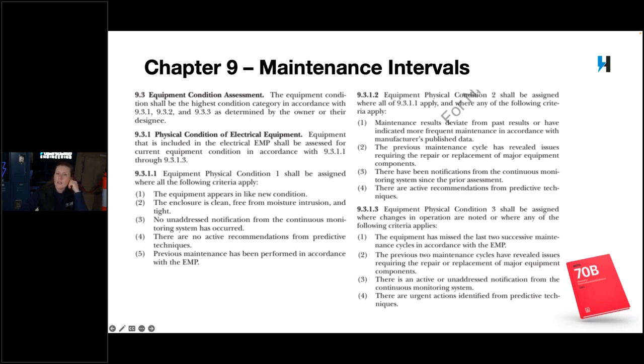Condition 2 is that there might have been something wrong - it's had a maintenance result that deviated from past results, indicating a potential problem that's beginning or has already happened, and we need to check on this a little more often. A lot of the other maintenance requirements decrease the time frame - you're doing it more often for condition 2 - but for infrared, it's still just your annual thing. That's bare minimum, by the way. Condition 3, though, if you've missed the last 2 required maintenance cycles according to what's in the book and your manufacturer's requirements, it's already condition 3.